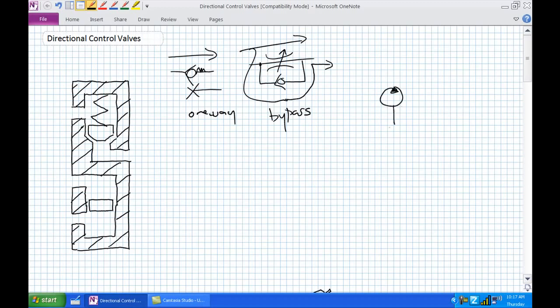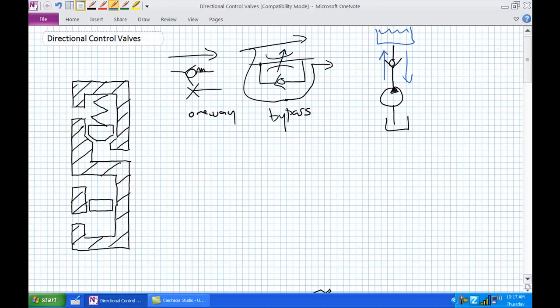Here's another application. Here's a pump — you've expended all that time to get fluid into a passageway. Sometimes you want to ensure there's a prime; basically all that fluid that's been lifted up so that when you turn the pump off, you don't want it to drain back through the pump. The check valve allows fluid flow in one direction but stops it in the other, basically keeping prime.